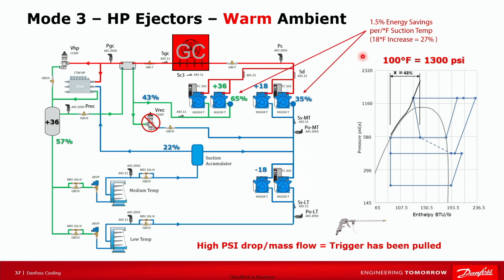So at that point, with the ejector block working on a warm day in parallel compression, 65% of your overall mass flow is being handled at almost 30% better efficiency than it would be without the parallel compressors and the ejector block. So here, if you'll remember, we got 43% efficiency before without being able to pull the 22% over. So with no ejector block, 43% efficiency, add the ejector block, you're getting 65% back up to that higher efficiency. And that's really the purpose of ejectors.